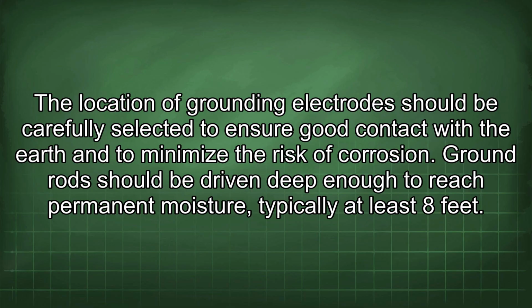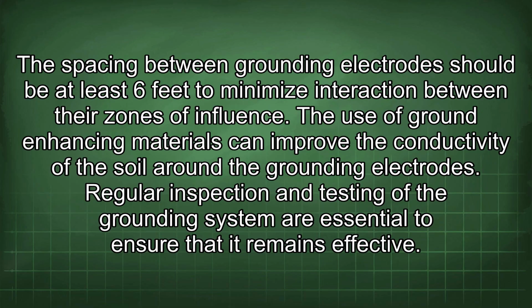The location of grounding electrodes should be carefully selected to ensure good contact with the earth and to minimize the risk of corrosion. The ground rod should be driven deep enough to reach permanent moisture, typically at least 8 feet. The spacing between grounding electrodes should be at least 6 feet to minimize interaction between their zones of influence. The use of ground-enhancing materials can improve the conductivity of the soil around the grounding electrodes.